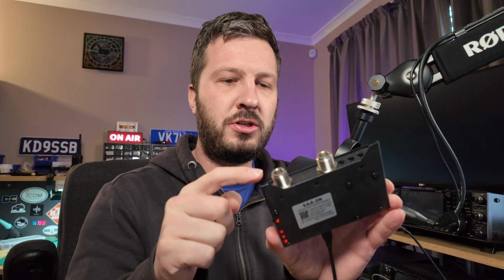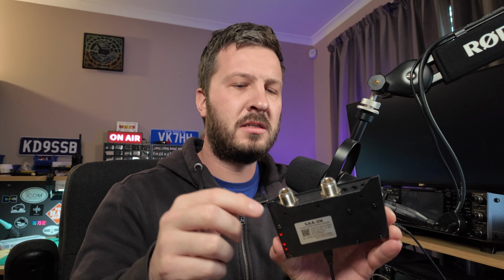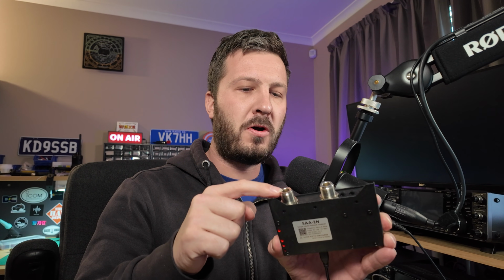The other thing to note is that I've calibrated it to the end of this port. That means that everything from here onwards is going to be measured, so from here to the antenna, which includes the coax as well. There's a bonus hint here: if you hook up your coax and you can access the other end of it, you can put your calibration standards at the other end of the cable, calibrate it, and then connect your antenna.